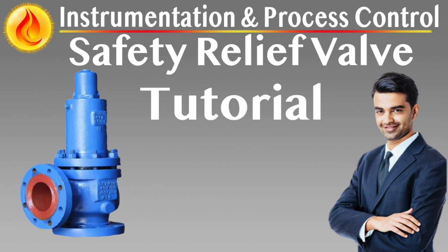Instrumentation and reliability considerations. Instrumentation reliability is critical to overall valve performance. In all modes, fail-safe design ensures the valve will still relieve pressure under mechanical spring action if pneumatic systems fail. Redundancy and interlock should be incorporated in safety-critical systems with diagnostics for actuator performance and pressure supply integrity. Pneumatic supply must be dry and clean to prevent actuator fouling or freezing. Fail-safe vented, ensuring actuator release during emergency shutdown.